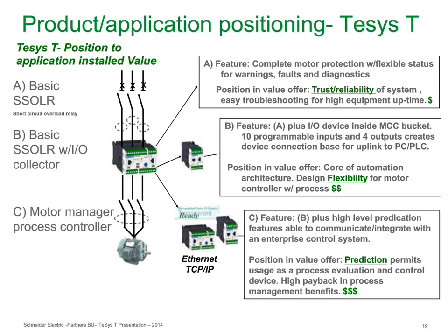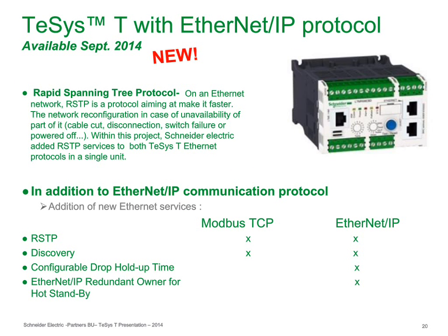Talked about some new additions, and actually we're looking to have this in August for launch in September, is the new TeSys T that has Ethernet IP protocol. One of the things for those folks that do process control, the new TeSys T with the Ethernet IP protocol will do both Modbus TCP IP and Ethernet IP in one device, and we do that through the software. But we've also added rapid spanning tree protocol into this device.